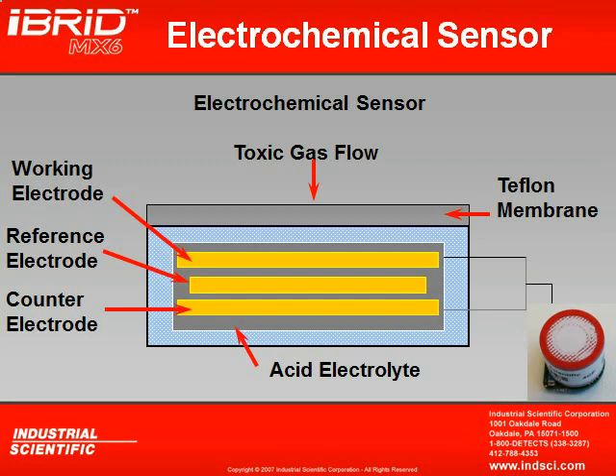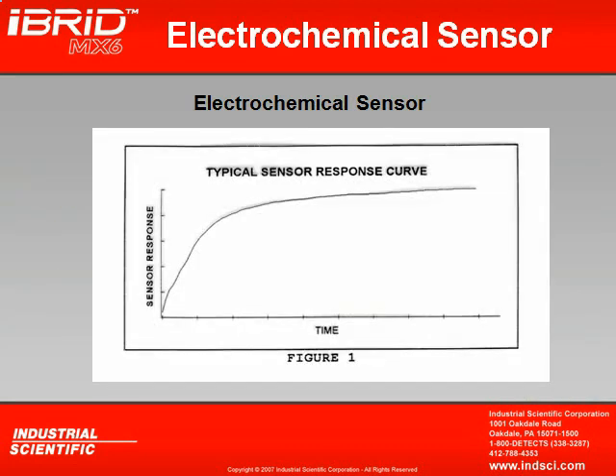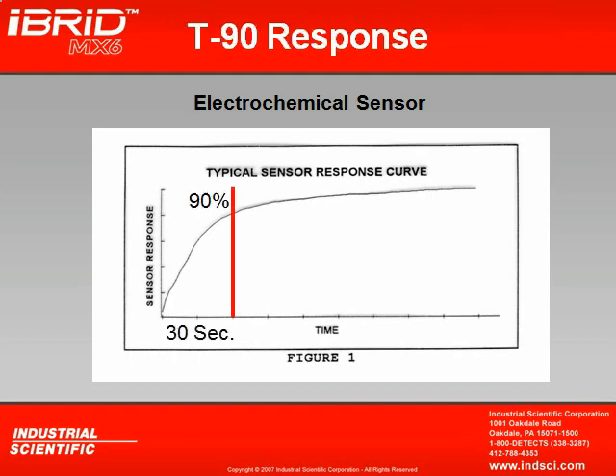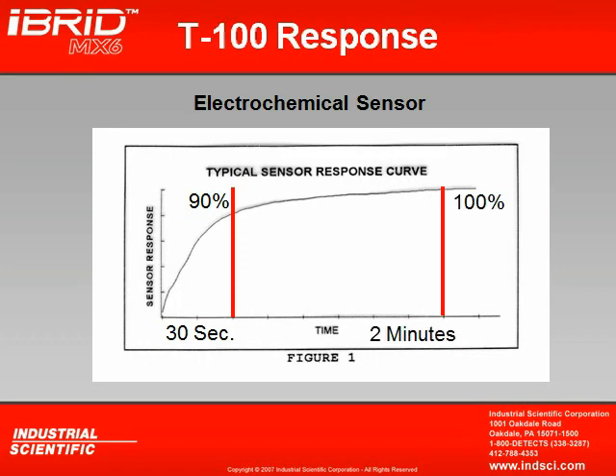Now the reading will not appear instantly on the display of the instrument when you're dealing with electrochemical sensors. It takes a little bit of time for that reading to appear. This is what we call the T90. This is the amount of time it takes for 90% response. Typically on a new electrochemical sensor, we're going to receive 90% of that response within the first 30 seconds. But it may take as long as 2 minutes to get the entire reading on the display of my instrument.